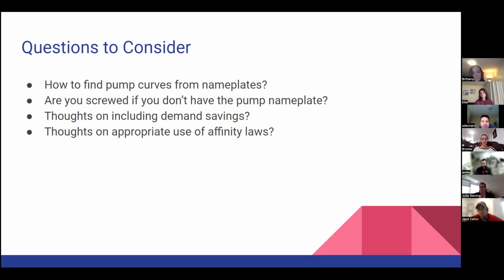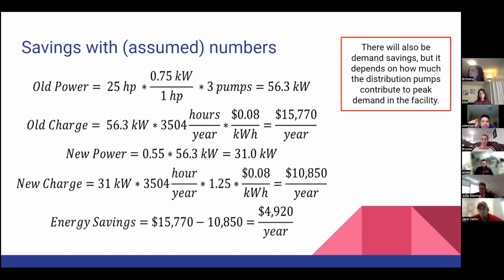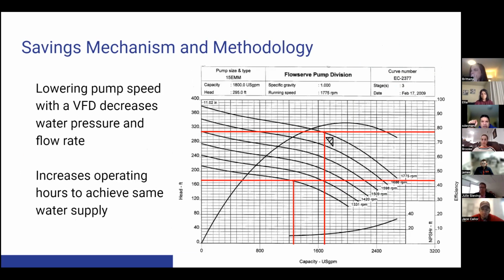Next thing, go back to the pump curve slide. I want to cover one topic here that you should be aware of. Was this cooling tower at an elevated point from this pump? Was the cooling tower on the top of a building and the pump in the basement of the building? No? Okay, keep that in mind. Because like this curve shows, your pump head drops. You must make sure that there's enough, because a cooling tower is an open loop system, your water has to overcome the vertical column of the pipe, right? It has to overcome a fixed head. Otherwise, the water is going to stall in the pipe and never reach the cooling tower.